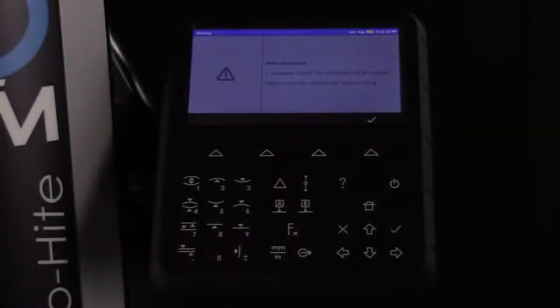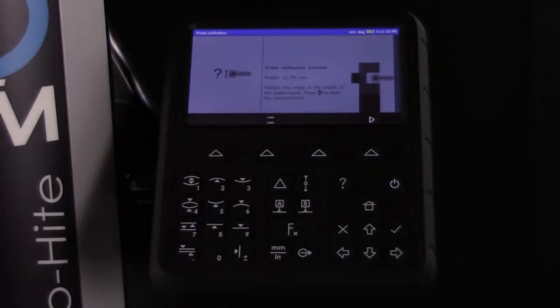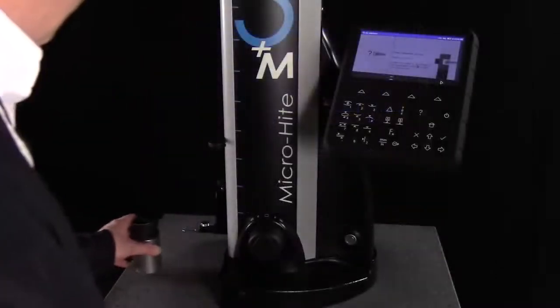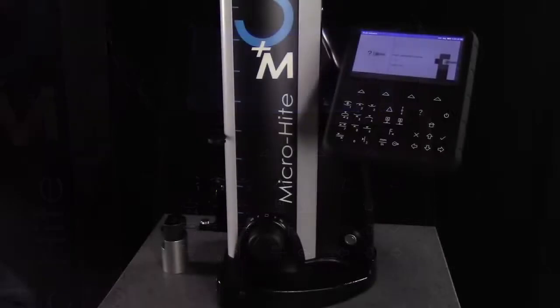Next, the display will indicate that it's time to calibrate the probe using the masterpiece. Move all other parts away from the probe and position the masterpiece for calibration. Then press the right arrow button on the display to begin the calibration sequence.